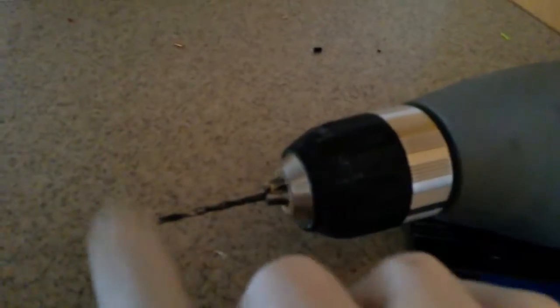Again. It tucks underneath this lip. All the wires are in. The armored. The BX cable is clamped in. So now there's a hole there. And there's a hole there. And when you lift this up. There'll be a hole at this end. And at the other end. That's how you're going to mount that to here. So what you'll have to do is. You'll have to drill in a pilot hole. That's where the drill comes in. Three thirty seconds. So what I'm going to do is. I'm just going to hold this up. And just drill through that opening. Until I bite into some of this wood. Move the unit out of the way. And then. Drive the screw in part way. Do the same thing on the other side. So that. When I go to install this unit. The screws will just drive in really easy.